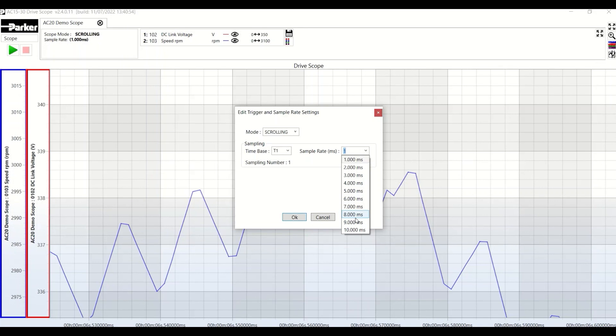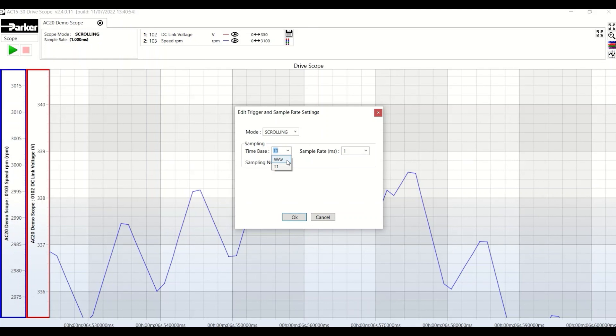If you were to record over half an hour, or even an hour, that would create quite large files. So one millisecond will suffice. An alternative selection is WAV. WAV synchronises sampling with the switching frequency of the drive. For example, when one switch is at 4kHz, which is parameter 412 of the drive, we will have a minimum sampling time of 125 microseconds — that is to say, 250 microseconds is the period for 4kHz, but we halve that to get 125 microseconds. This allows for more precise observation of the signals. One millisecond will suffice in most cases.